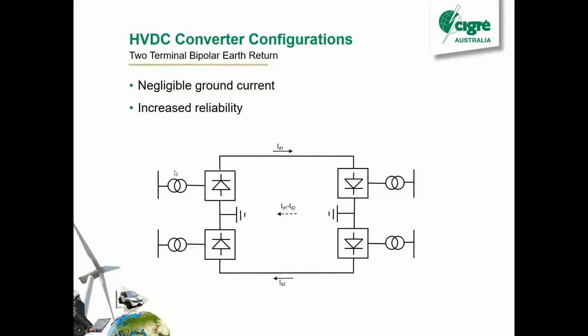So we've got two poles here with the earth in the middle. One pole runs at positive polarity, the other pole runs at negative polarity, and you have this current that goes, and the current always goes in the same direction around the loop, regardless of which way you're sending power. And if you want to change the power direction, you change the voltage on your conductor.